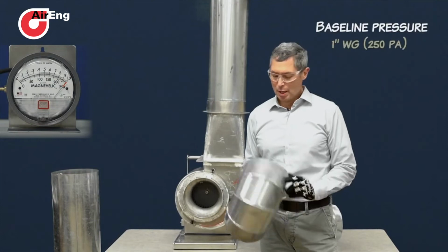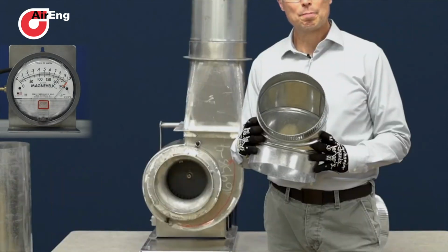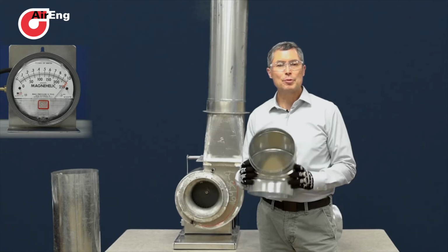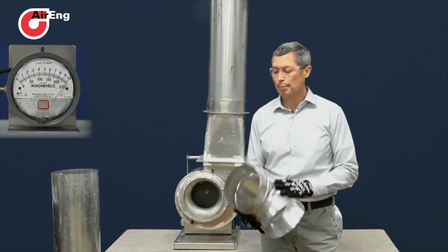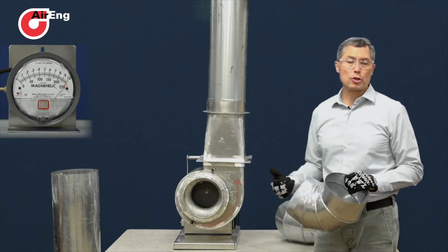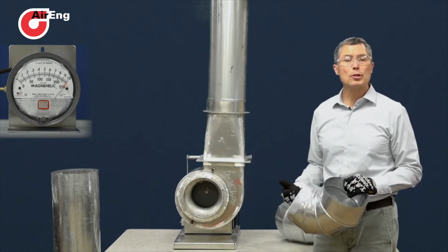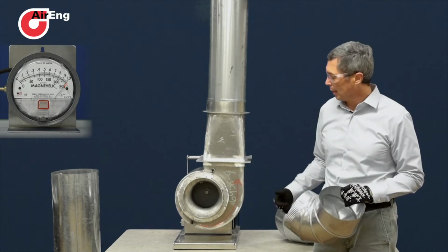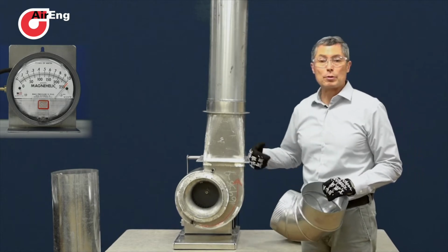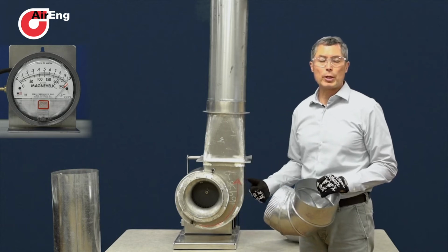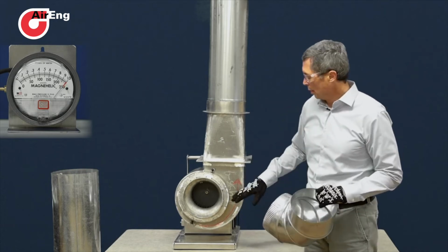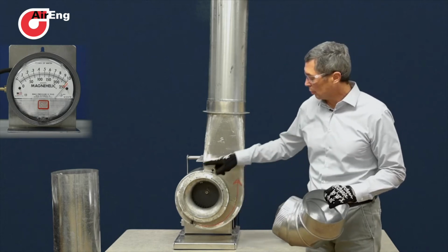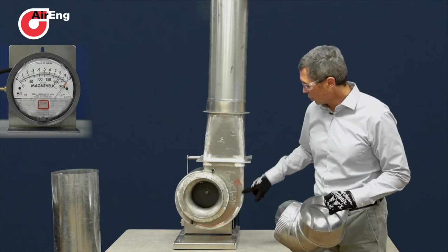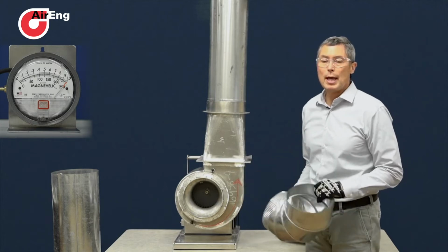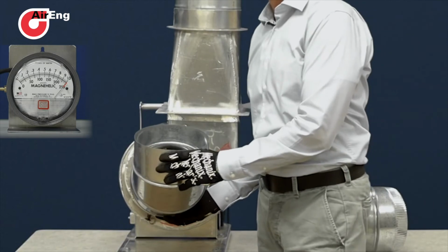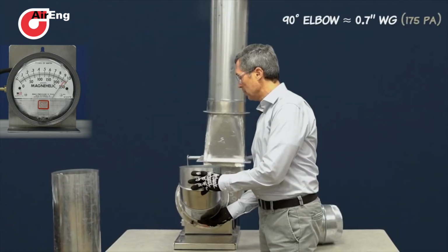Live demonstration time. Well, we have two 90-degree elbows, just straight 90-degree elbows, nothing inside of them, no turning vanes, no obstructions. And we're going to connect them in a corkscrew effect that's going to either pre-spin or counterspin the air as it enters the fan. When we talk about that, we're talking about whether it's rotating air in the same direction as wheel rotation or against the wheel rotation. Wheels rotate in the same way the volute shape of the housing expands. So I drew this nice little arrow here to show the wheel rotation, and we're going to simply see first how a fan is affected by counterspinning the air.